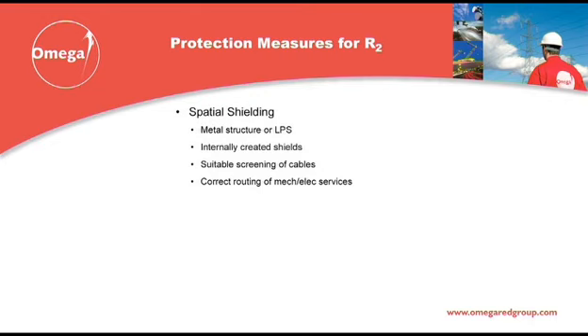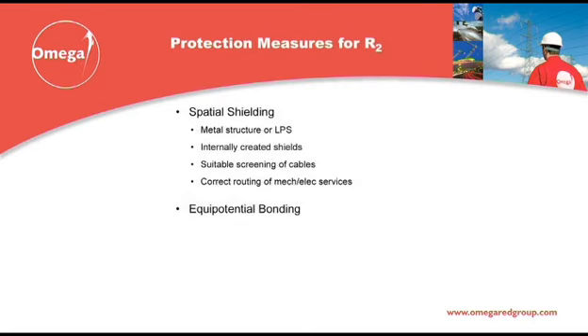The limiting effect of these measures is taken into account as part of the risk assessment process, and it is important that accurate building service information is provided to the engineer undertaking the risk assessment so that it can be appropriately considered. The choice and layout of bonding systems are crucial to the protection of electronic equipment. Each zone needs to ensure equipotentialisation within it by the provision of an earth bar at the entry point to each zone.